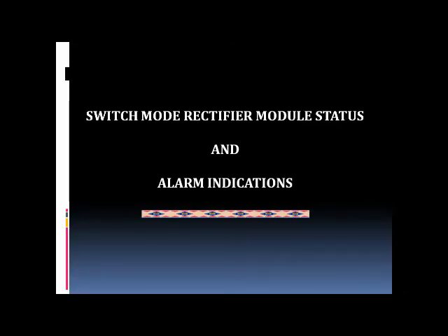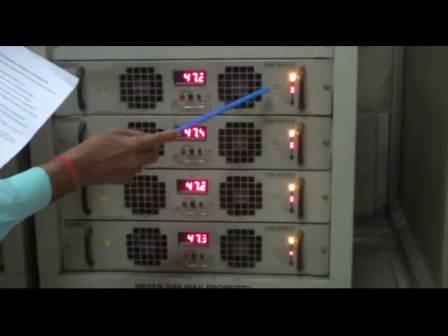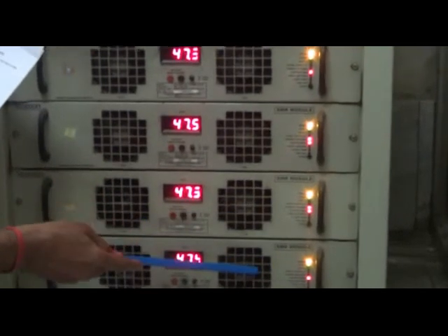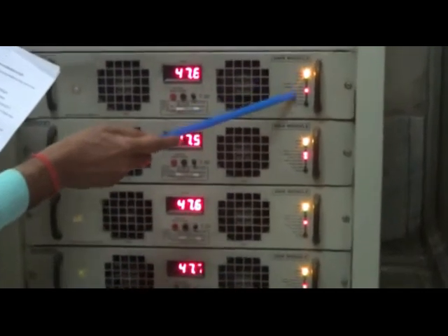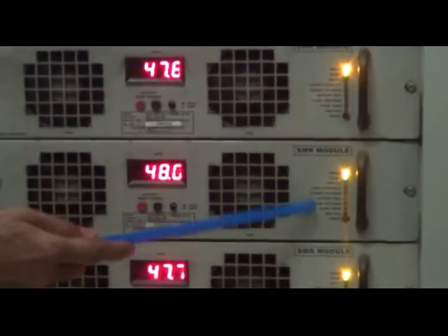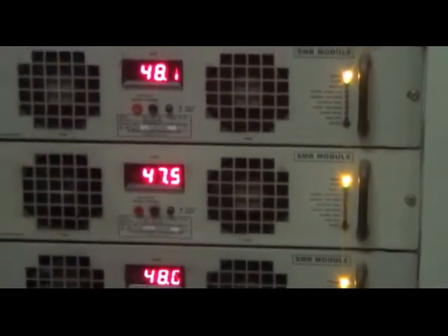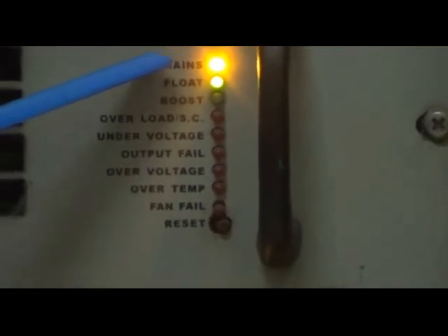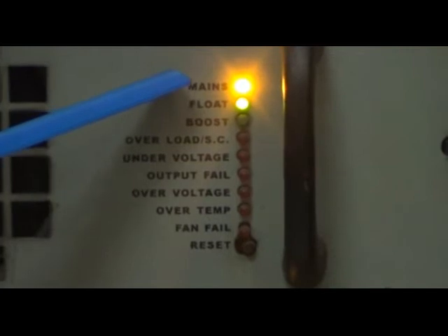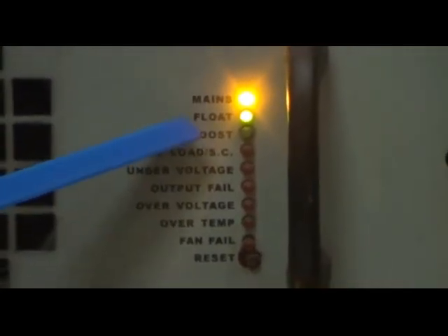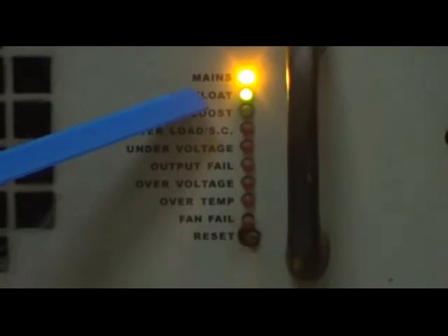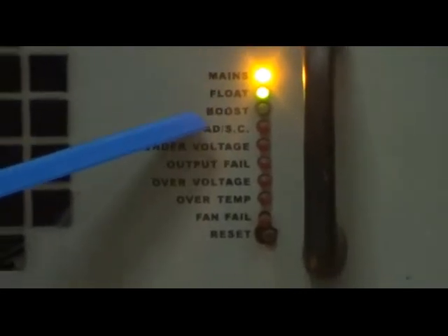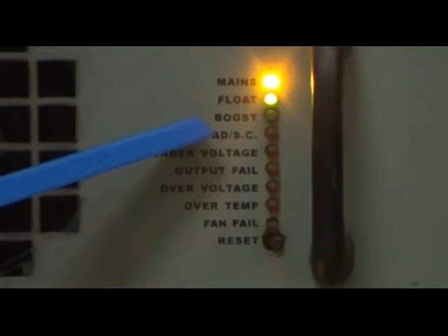Switch Mode Rectifier Module Status and Alarm Indication. This power supply has 4 SMRs. Following indication LEDs are provided on the front of each rectifier module. Mains: it indicates that mains supply of the module is on. Float: this indication shows that the module is in float mode of charging. Boost: this indication shows that the module is in boost mode of charging.